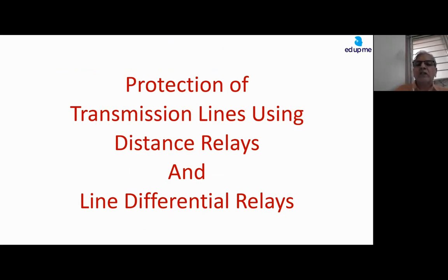Second thing, in an interconnected system, it becomes very difficult to set the relays. Many researches are going on how to coordinate the relays in the interconnected system, and yet certain mal operations are bound to happen. These mal operations are tagged as sympathy trips. Now I have been seeing in PhD theses, some gentleman has done his doctorate with an algorithm which gives three sympathy trips. And if I do my PhD with two sympathy trips, my PhD will be better because I have reduced sympathy trips. But yet, zero sympathy trip is not possible. That means mal operations occur when I protect the interconnected power system with overcurrent relays. Therefore, overcurrent relays have limitations.